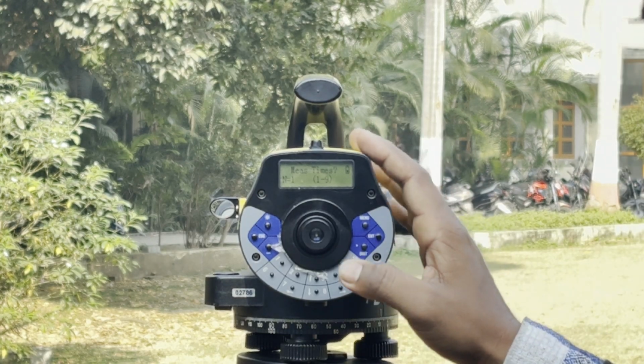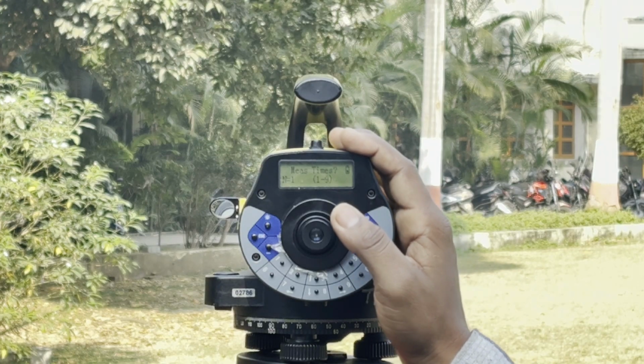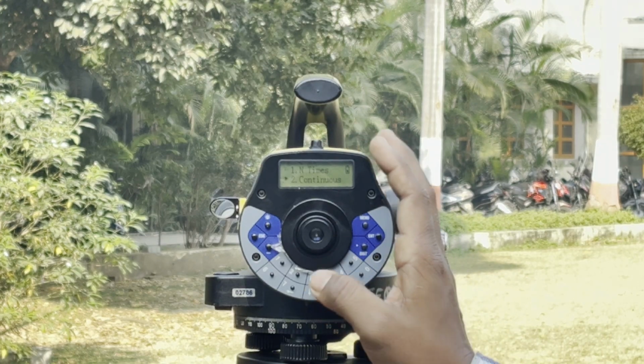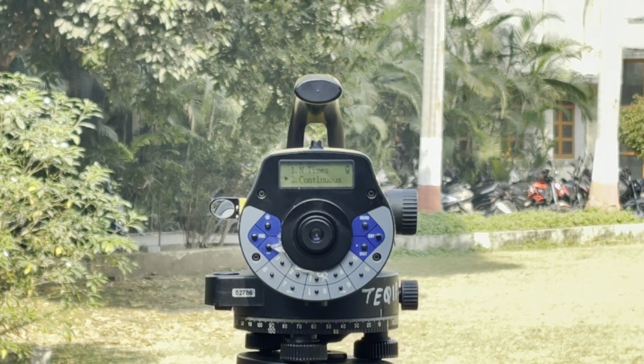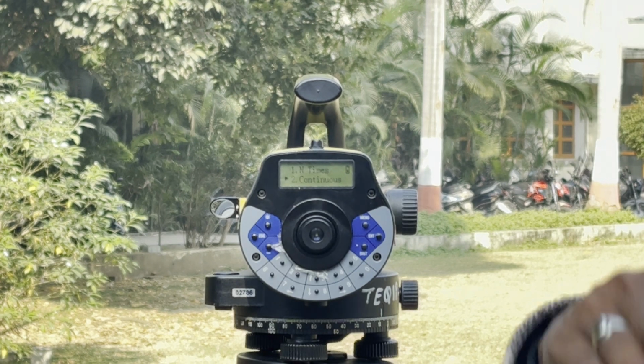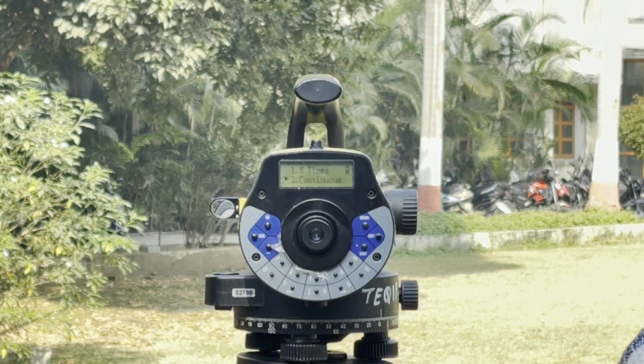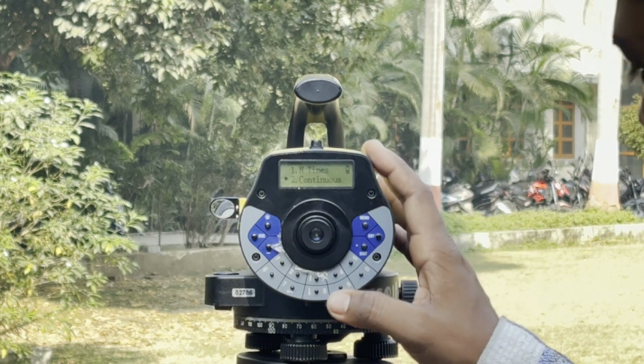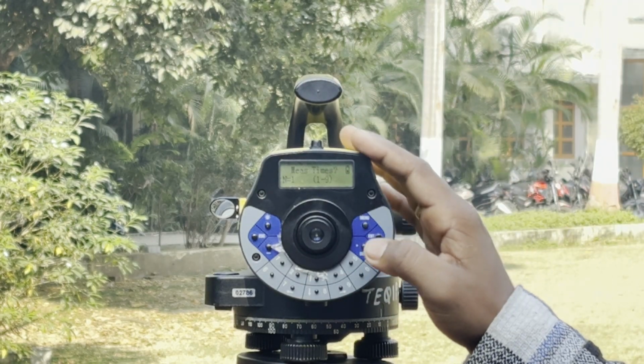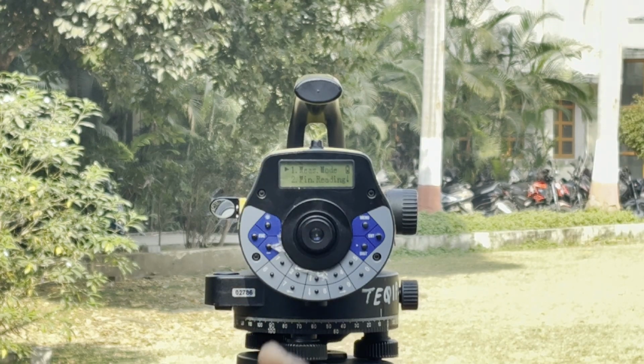Okay. Right now I choose n equal to 1. Then continuous. Right now no option is choosing number 2 option. No need to choose, because if you click on continue and press enter, the instrument is continuously reading or scanning the leveling staff or barcoded staff. But right now no need of that. Simply enter n time number 1, enter, and then escape.